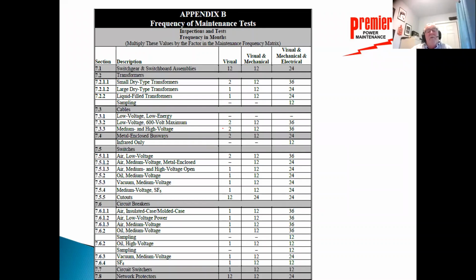And I can actually go to some other parts. Let's look at a liquid filled transformer. It says it needs to be visually inspected at least once a month. Somebody will look at that every month. Visually and mechanically inspect it, just make sure it physically is in good shape, the grounding connections and those sorts of things, every 12 months.